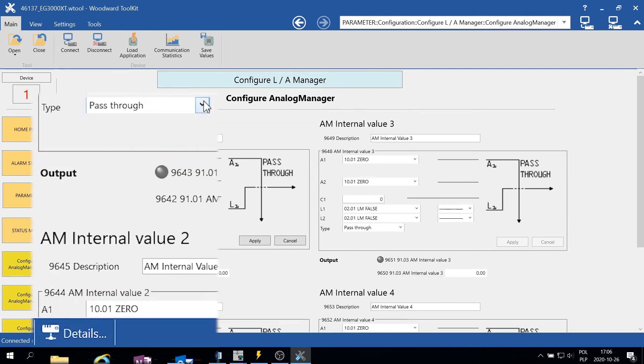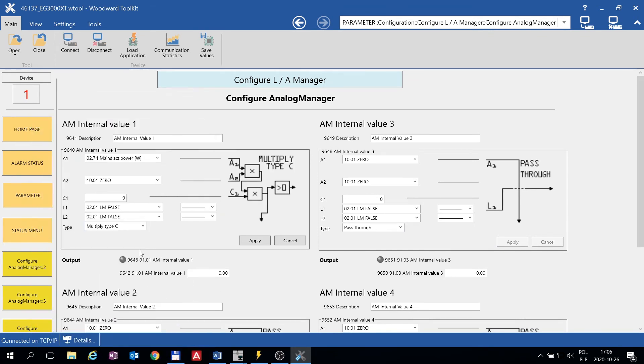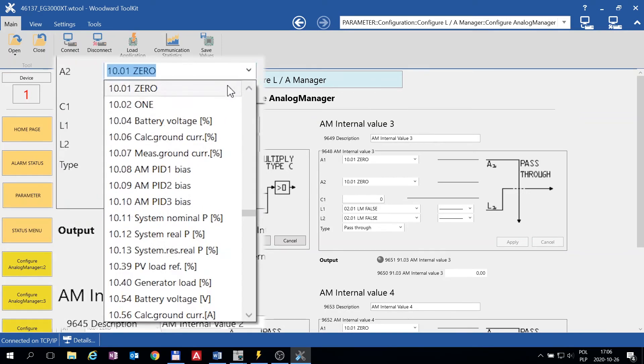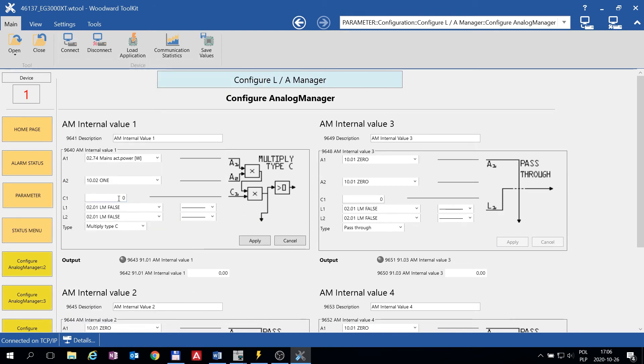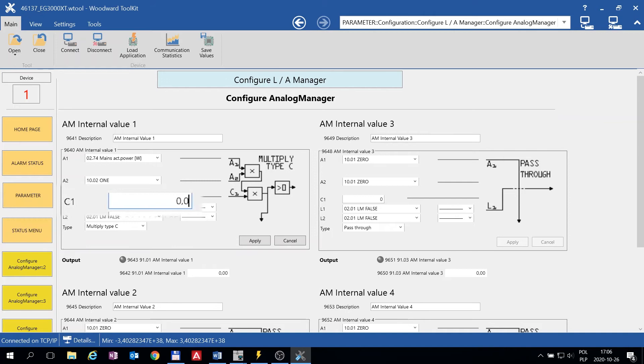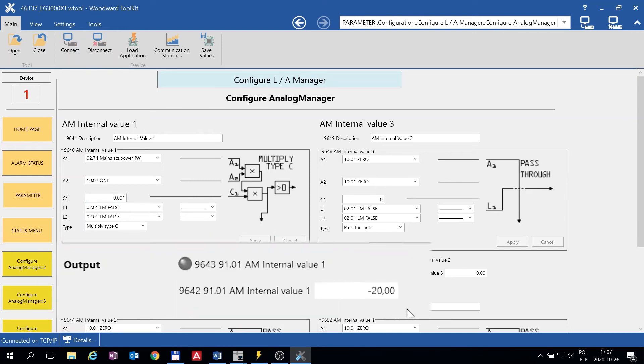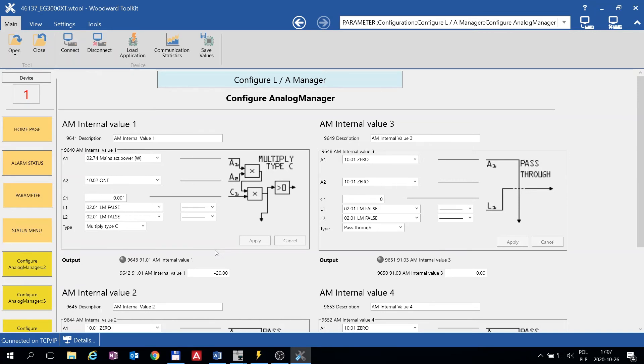Here we need to multiply this, so let's choose Multiply function. The other input we should choose as 1, and here we enter our constant to change the value to Kilowatts. After that we click Apply, and here we can see that we import 20 Kilowatts right now from mains.